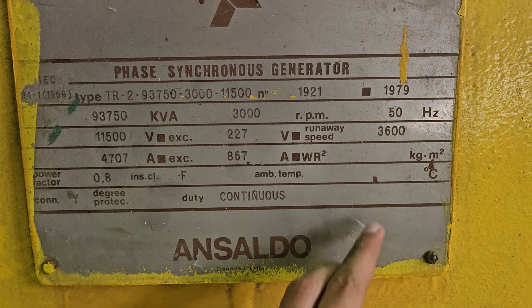It was manufactured by Ansaldo, and this is the nameplate of the generator. As you can see, it is a synchronous generator manufactured in 1979, and it generates output power of 93,750 kVA and output voltage of 11,500 volts. It requires an excitation voltage of 227 volts. It runs at 3,000 RPM. The power factor is 0.8, and the insulation class of the winding is F.